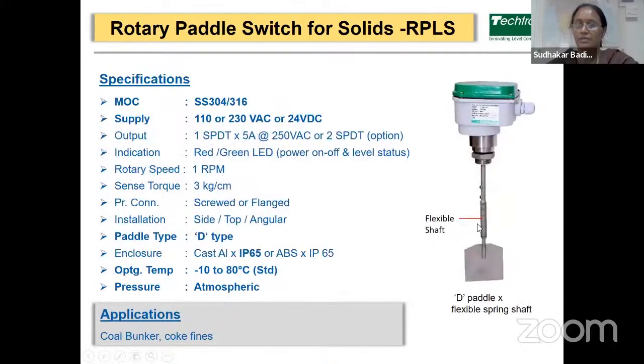So on the right hand side, you can see the flexible shaft. Then material will be in SS304 or SS316. The supply for this switch is 110 volt AC or 230 volt AC or 24 volt DC. The outputs are available as SPDT contacts or two SPDT contacts, which are suitable for 5 ampere 250 volt AC ratings. The rotary speed of this paddle or the motor is 1 RPM, that is 1 revolution per minute. The process connections are available as screwed or flange connections. The paddle type is a D-type paddle. Then enclosures are available as IP65 protected. Operating temperature is minus 10 to 80 degrees Celsius, and pressure is atmospheric. They are generally used in coal bunkers or coke fines.